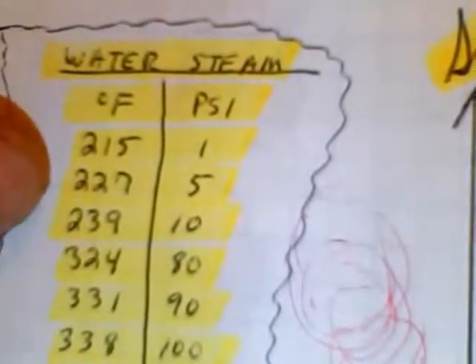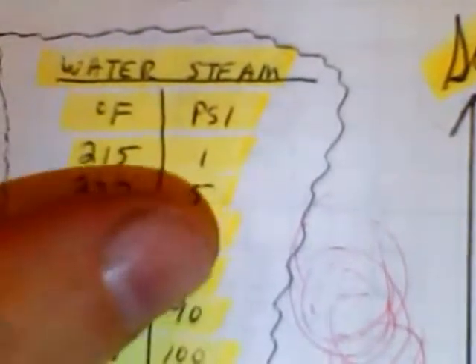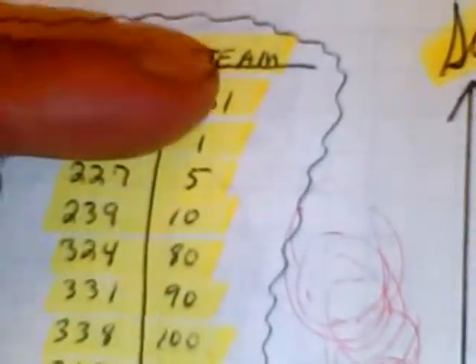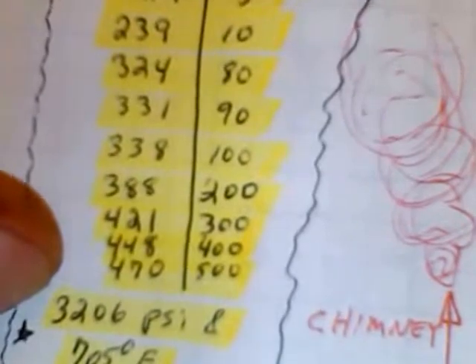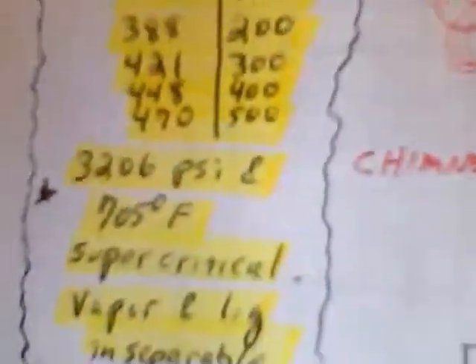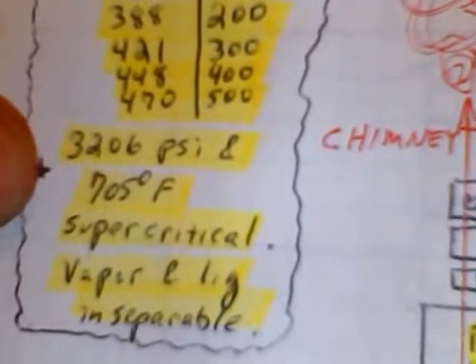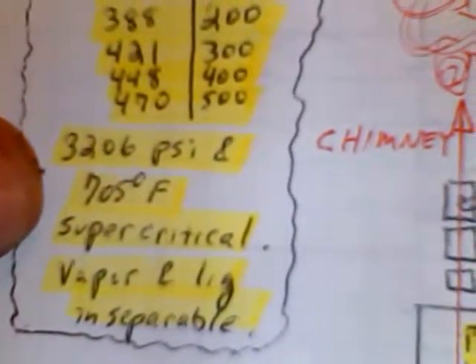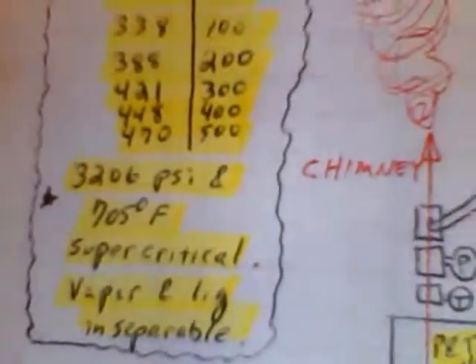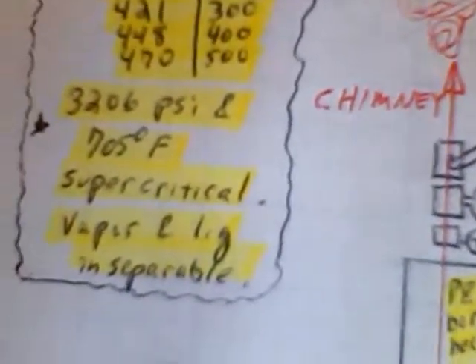I have the water and water temperature. Look at your different water temperature and your steam pressure values. Here's 215, you have 1 psi on water. Take it all the way down to 470 Fahrenheit, you're about 500 psi on water. So it's very dangerous to be working with steam, and that's on water. At 3206 psi and 705 degrees Fahrenheit, that's where you're super critical on water. The vapor and liquid are inseparable at that point.